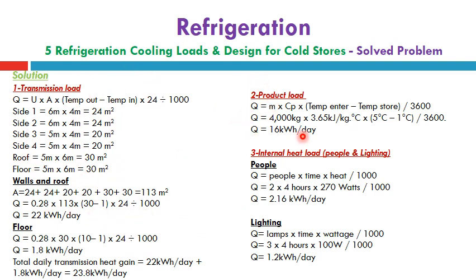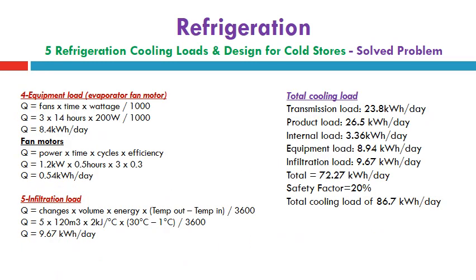Then the product load is calculated from the temperature difference between the entering and store temperature, the specific heat of the arriving apples, and the mass of apples, divided by 3600 to get the product load per day. Then the internal heat loads such as people and lighting are listed here, you can check. Then the equipment load, the evaporator fans, and the infiltration load. Finally, you can estimate the total cooling load based on the summation of these components: transmission, product, internal and equipment load, and the infiltration load. Then you can take a safety factor of 20% to get the total cooling load of this cold store, which is equal to 86.7 kilowatt hour per day.